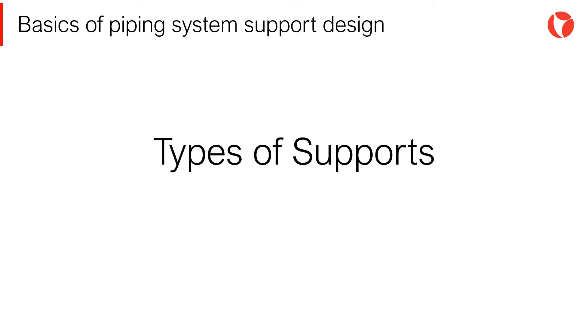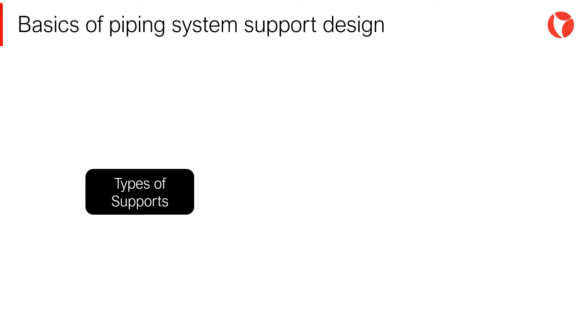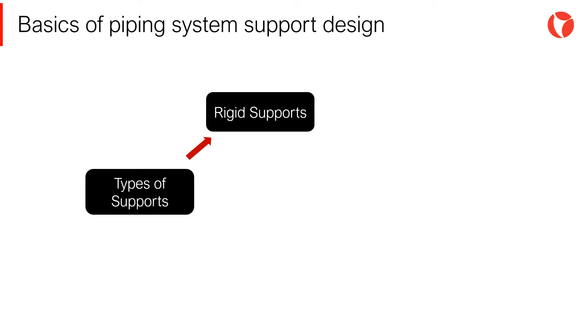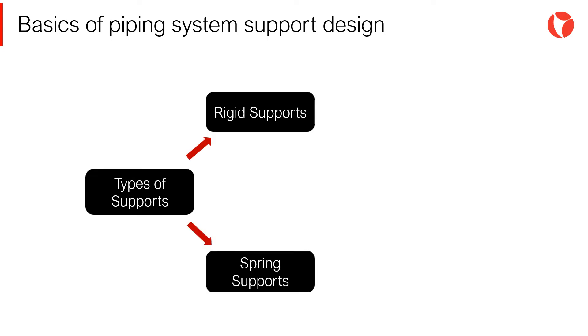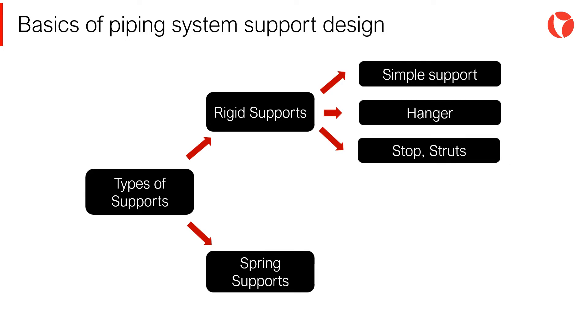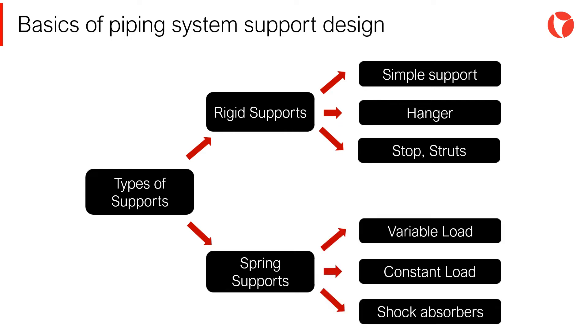Pipe supports are categorized according to the function and restriction they exert on a piping system. Supports are generally divided into rigid and spring supports. Within rigid supports we can find simple supports, hangers, struts, etc. Within spring supports we can find variable load, constant load, and shock absorbers.